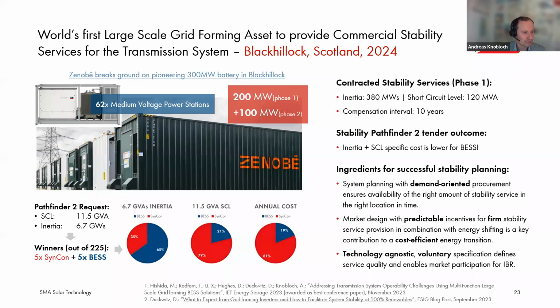And the winners have been chosen out of 225: 5 synchronous condensers and 5 battery energy storage systems. And we see the shares they cover: 35% of the inertia is covered by the synchronous condensers and 65% by battery energy storage systems. So it seems to be more effective to provide inertia by battery energy storage systems compared to synchronous condensers. On the other side, the short circuit level provision is more on the synchronous side compared to the battery storage side.